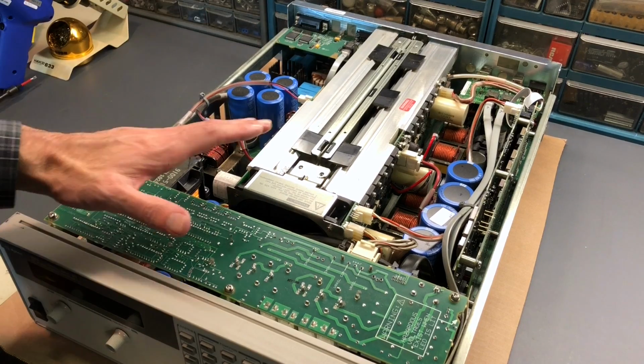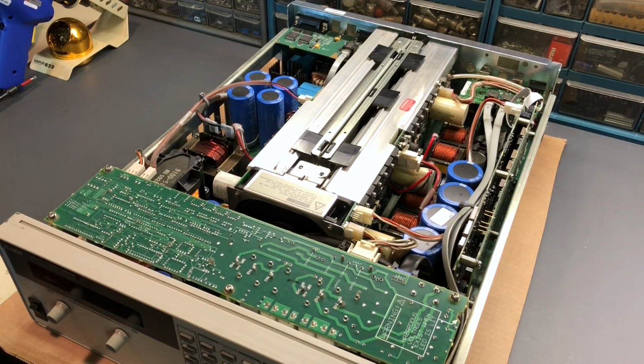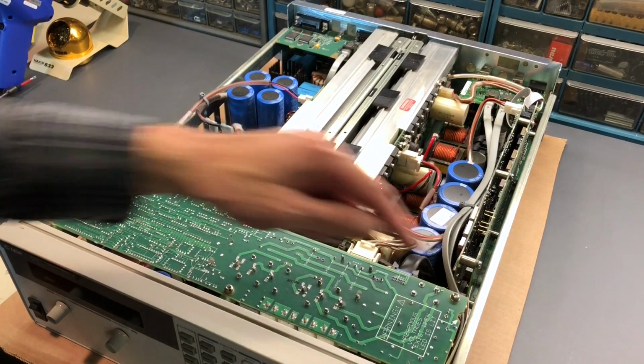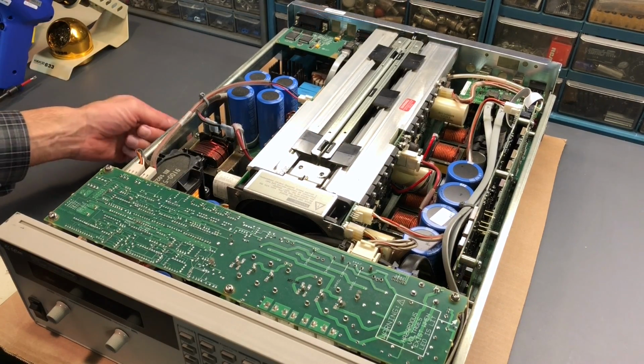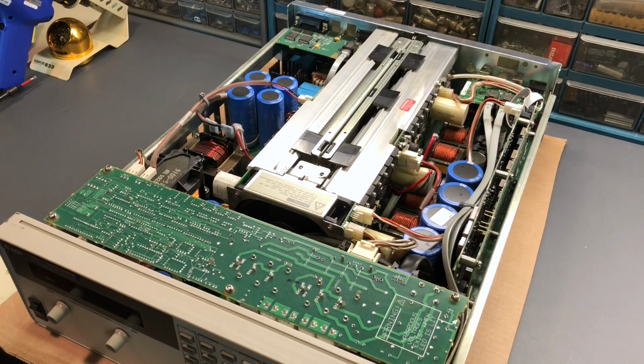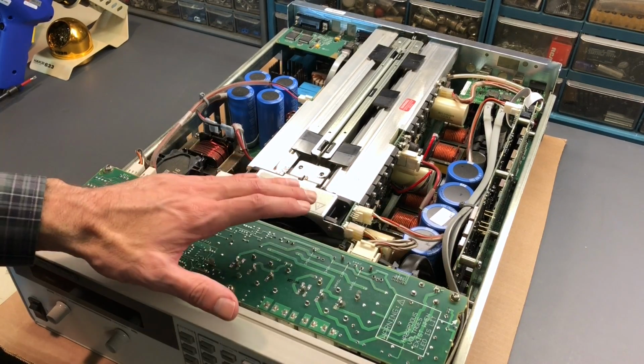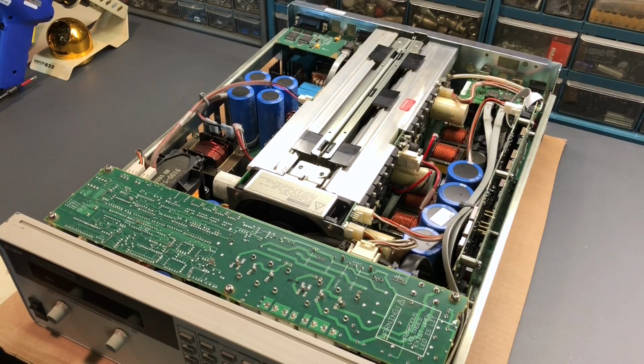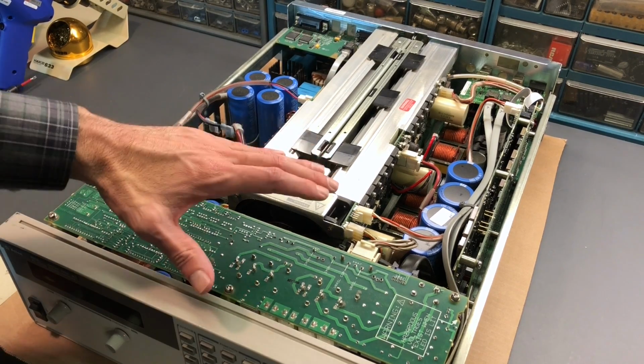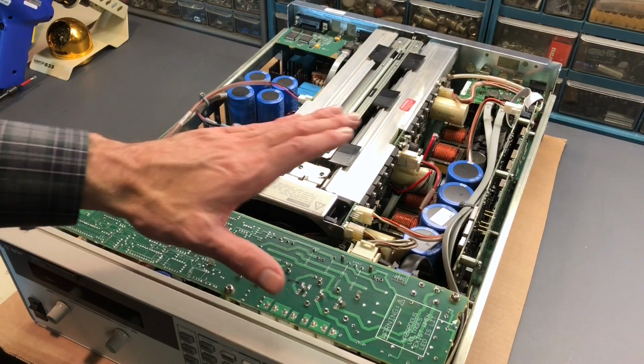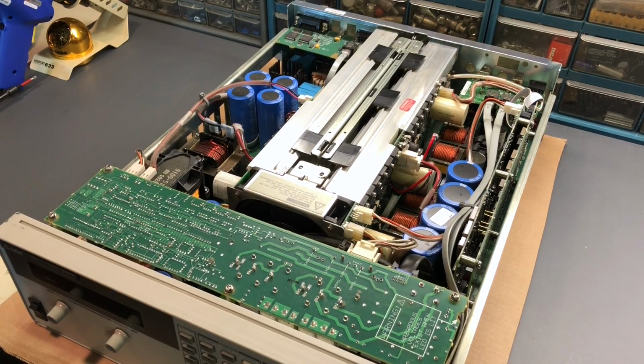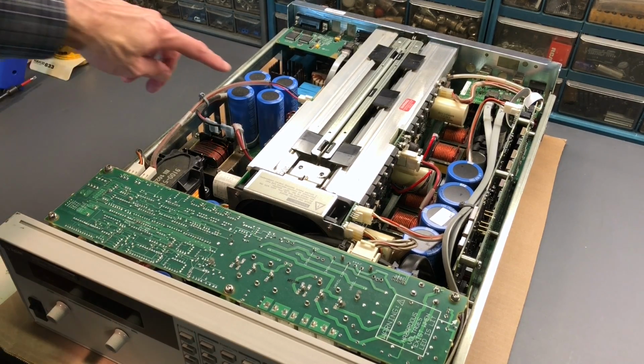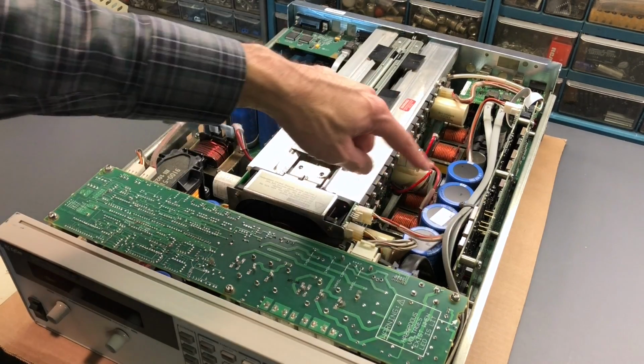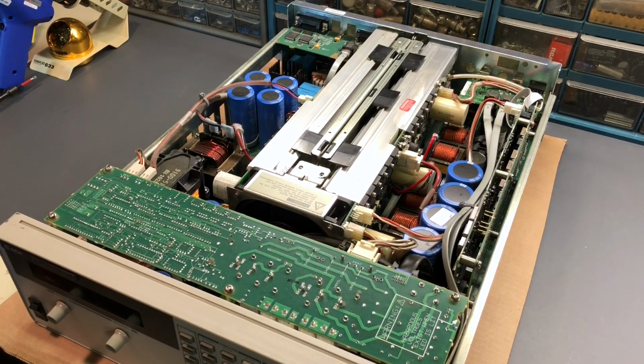Now, this has not been powered up in a long, long time. Everything's discharged, so there's no high voltage in here. There is an LED indicator right here, and then there's one on the side. It is right down here. And if those LED indicators are on, it means that there's high voltage present, so you definitely have to be very, very cautious. Again, this DC rail in this unit has 1,000 volts from the positive to the negative side, so extremely high voltage. You can see these very large electrolytic capacitors are everywhere in here. Those are going to hold a charge for a considerable amount of time after the unit is powered down.